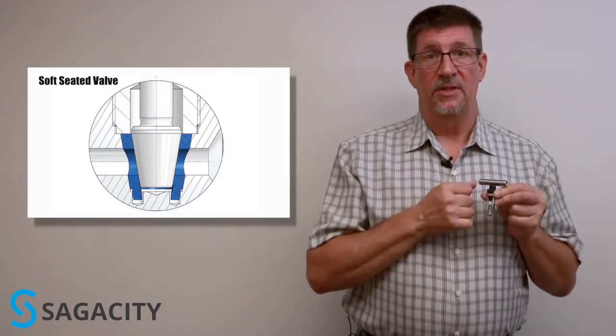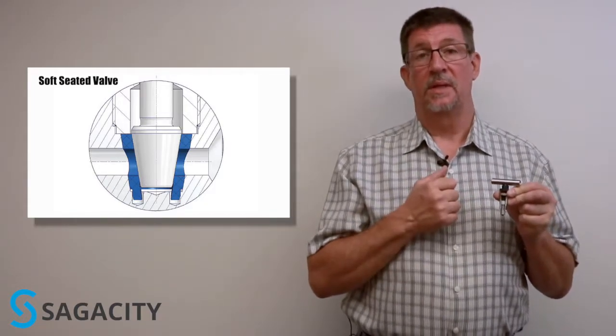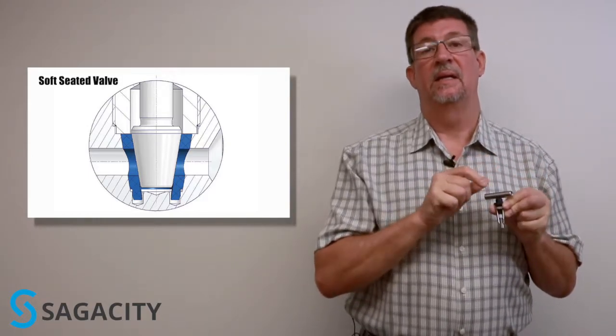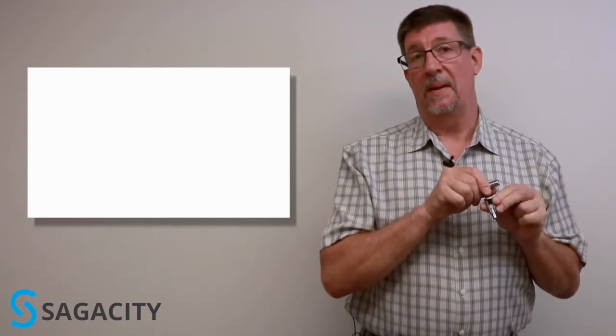For gas applications, you want a soft seat, like a Delrin plastic or a Teflon, so that the stem can actually sit and seal tight against the body of the valve.